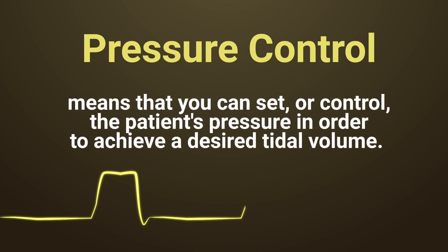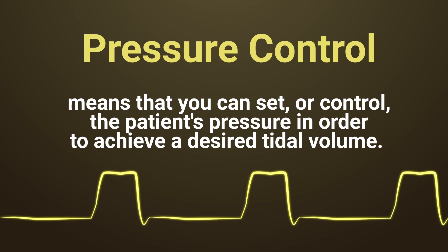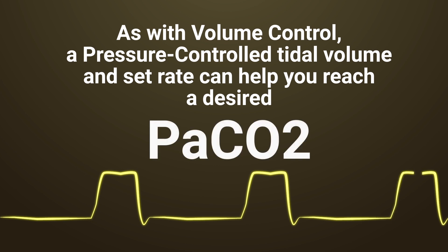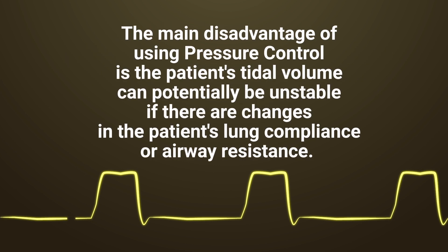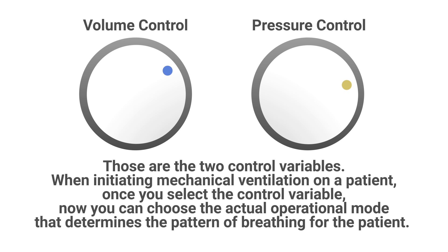Pressure control means that you can set or control the patient's pressure in order to achieve a desired tidal volume. As with volume control, a pressure-controlled tidal volume and set rate can help you reach a desired PaCO2. The main disadvantage of pressure control is that the patient's tidal volume can potentially be unstable if there are changes in lung compliance or airway resistance. So again, volume control and pressure control are the two control variables.